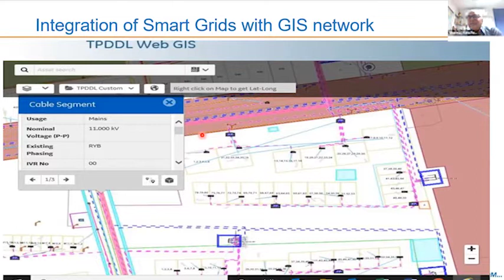So what we thought of was GPS to start with, but with the normal GPS we have in our mobile, the accuracy is 15 to 20 meters. But for electrical systems where we install our substations, cables and all those things, we cannot have a system which tells the cable is at this point or 15 meters here and there.